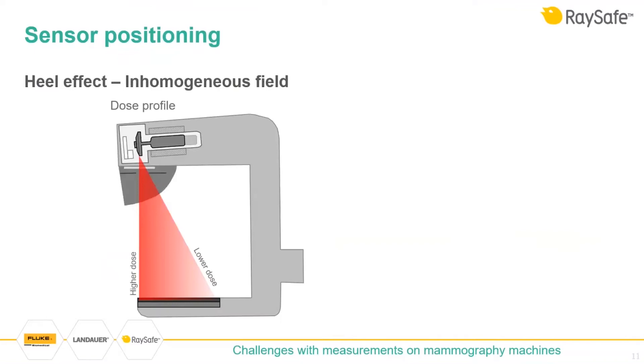Regarding the heel effect and inhomogeneous fields: the built-in heel effect of an X-ray tube is used to maximum advantage in mammography. The dose is highest at the chest wall side and can be 25% lower on the other side. The benefit is to compensate for the breast being thicker close to the chest wall. The challenge for measurement is that the exact positioning of the instrument becomes very important in order to compare data and know what is being measured.